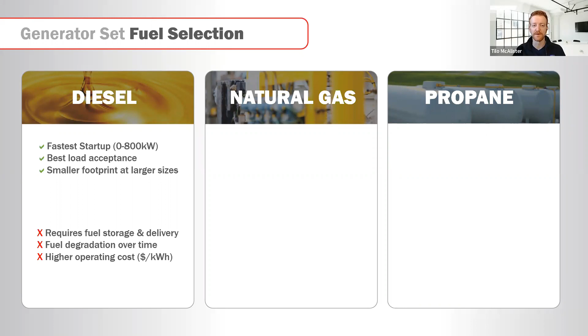That's one of the reasons we see a lot of favor to natural gas in the standby power market, not to mention continuous generators. The advantage there is that you don't require fuel storage on site if you have access to a pipeline connection, and you have a lower operating cost in terms of dollars per kilowatt hour of electricity. In general, they're quieter, and compared to diesel, they're a lot cleaner on the emission side as well. They do struggle with load acceptance compared to a diesel engine, and the larger natural gas engines have to be built quite a bit bigger than the diesels because of the tolerances and the heat of combusting the natural gas.